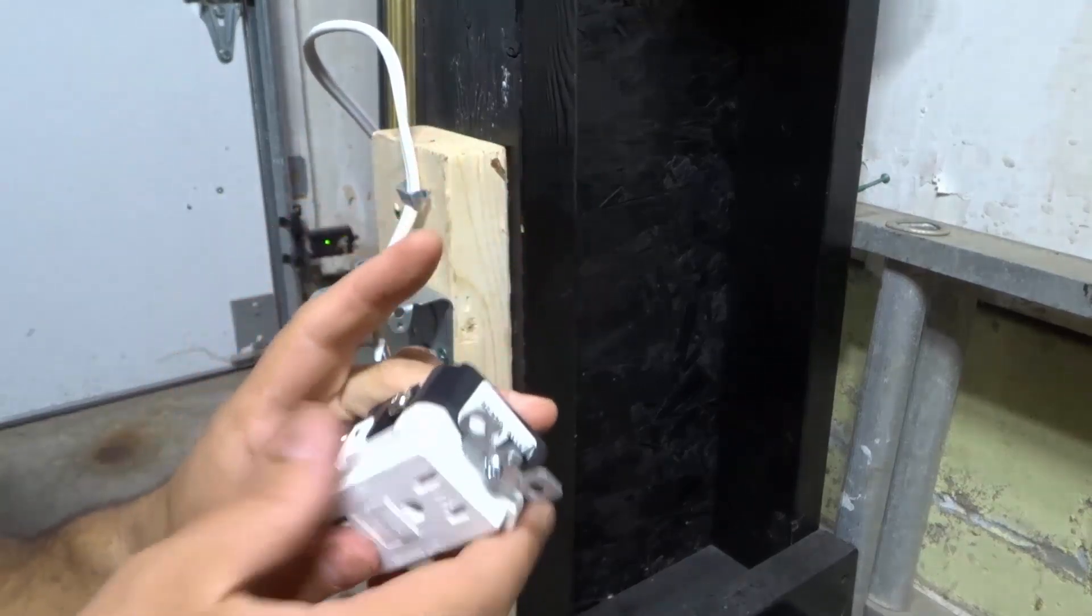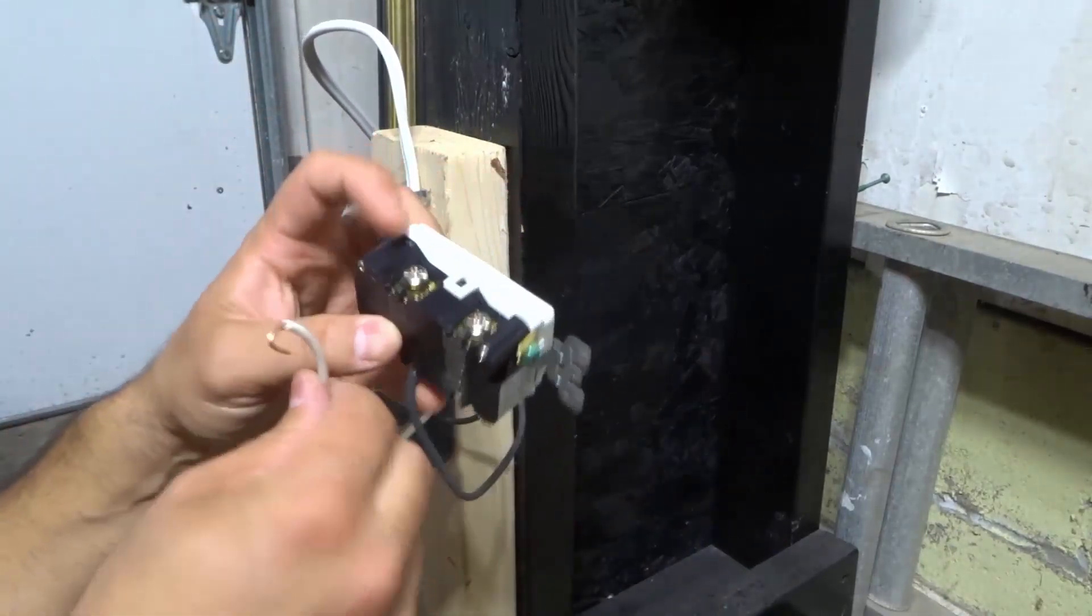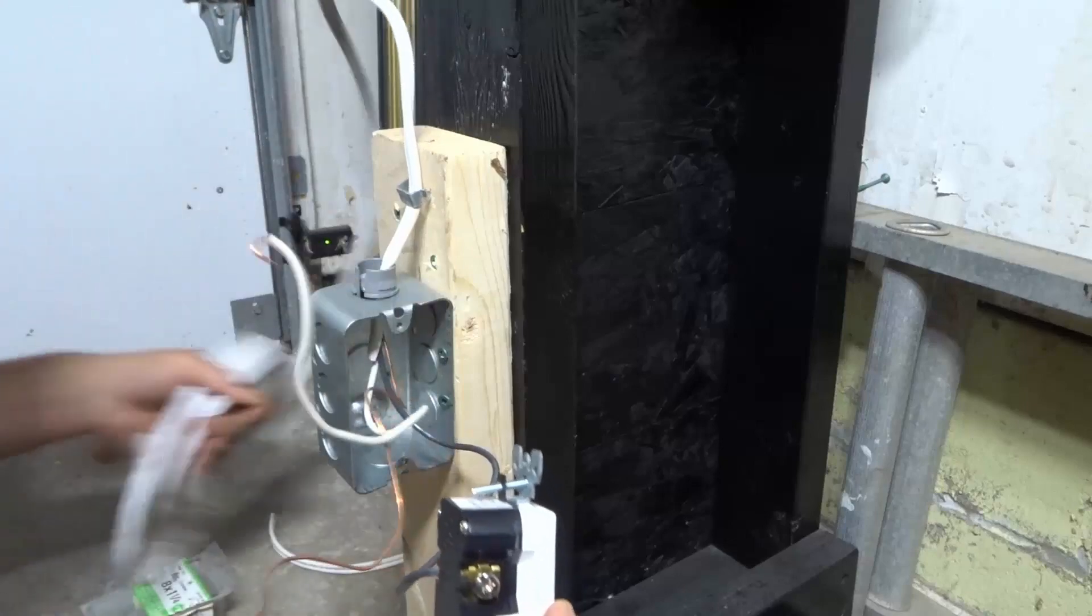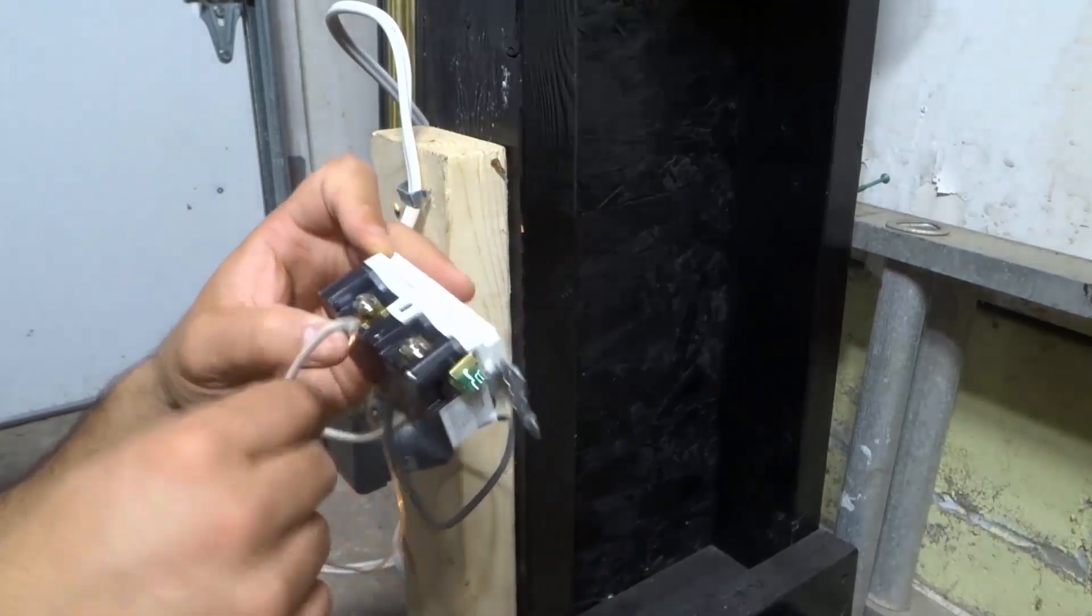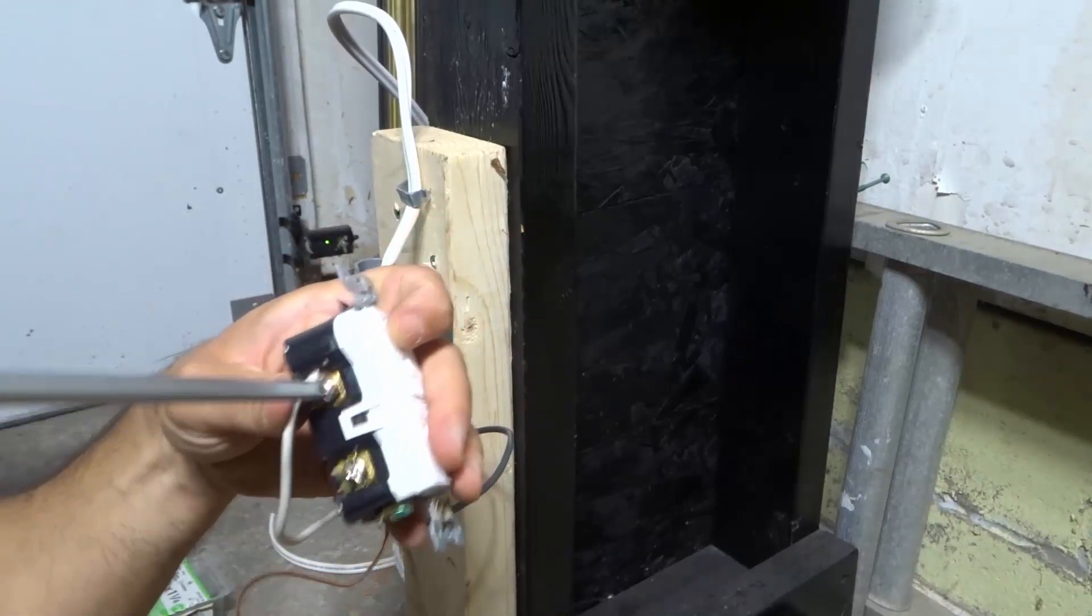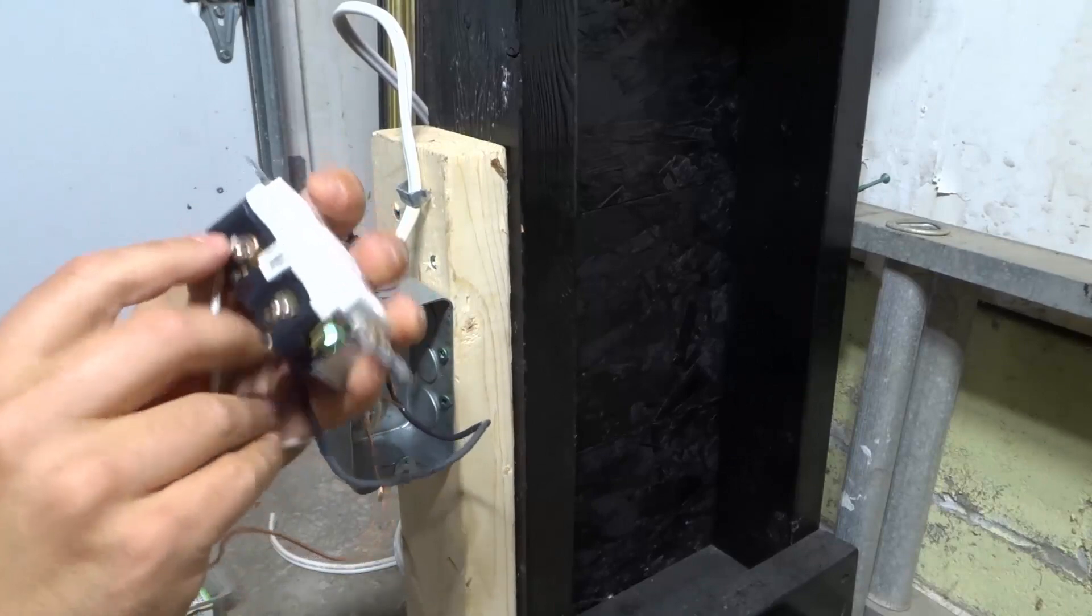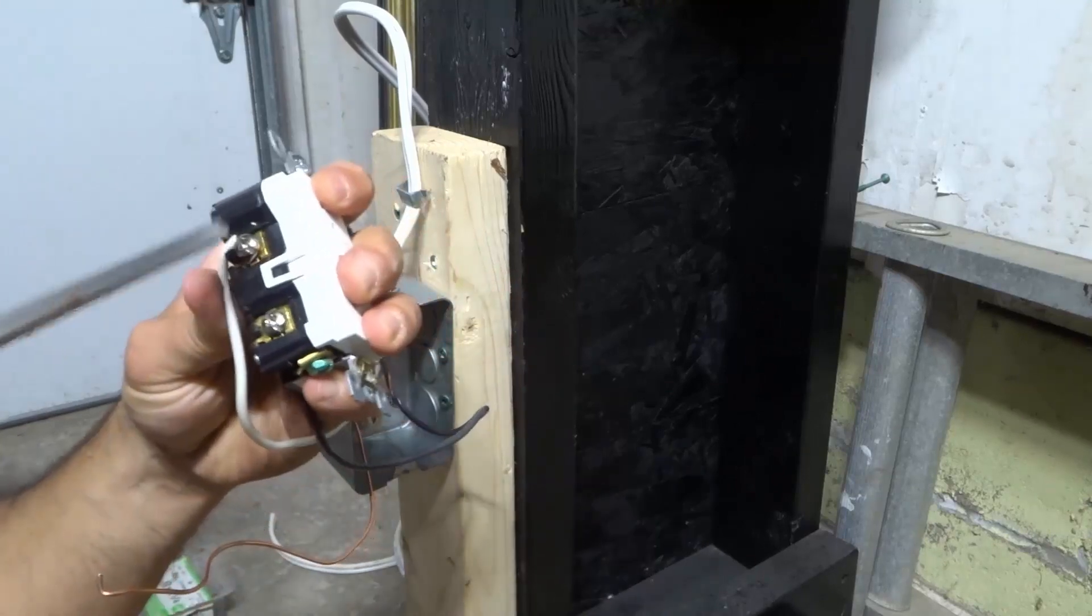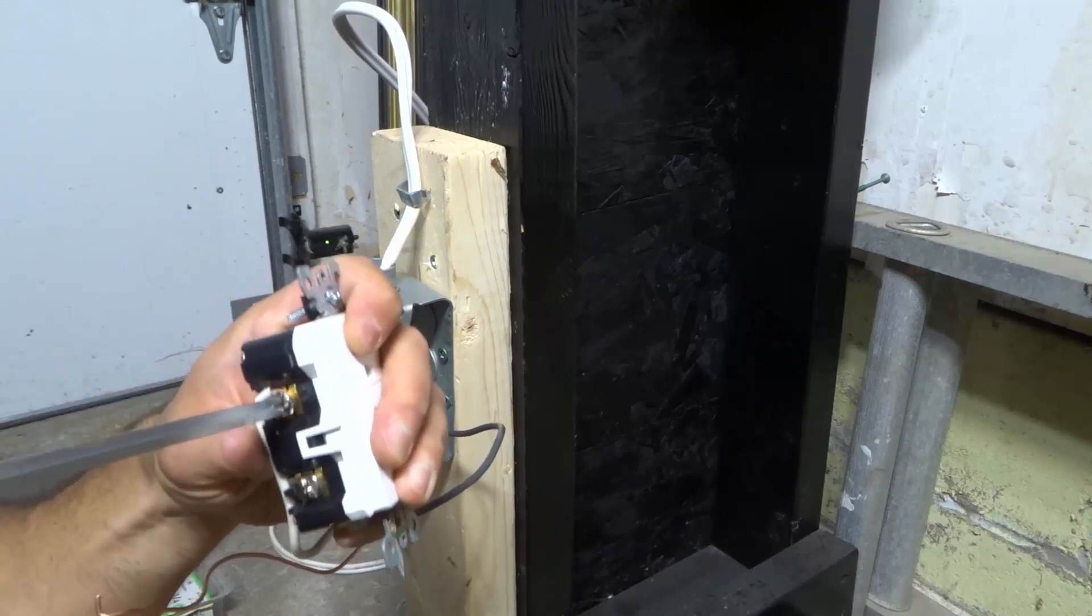Obviously the power is going to be off—this is not connected to anything. Make sure that your power is off. On the other side of the line side, you're going to see a silver colored screw which is for your neutral. Loop it around, make sure the loop is in the same direction of the tightening of the screw, and tighten that screw down. Don't be afraid to be generous with how tight you are tightening it. Make sure that loop is locked in there nicely—you see how the loop is tucked away behind the screw? That's the way you want it to be. You don't want the loop sticking out and at risk of being pulled out.